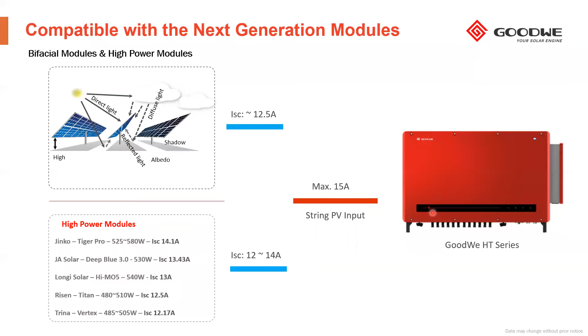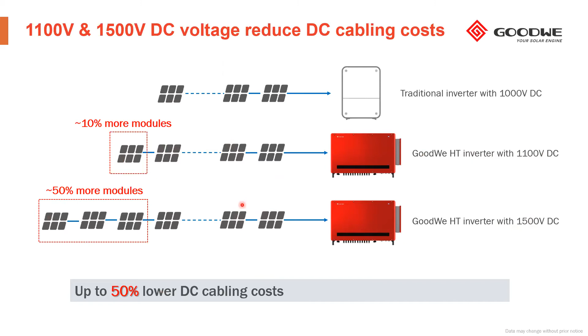I'm going to go faster here. I think everybody knows here that more or less in the market we work with 1000 volts, and in the C&I portfolio we work with 1100 volts, right? So that means that we can increase the number of modules per string. In case of our inverter 250 that operates with 1500 volts, of course we can make the string larger, and that gives us the chance to lower our investment in the DC cabling, and sometimes in the racking system as well, depending on the model that we use.